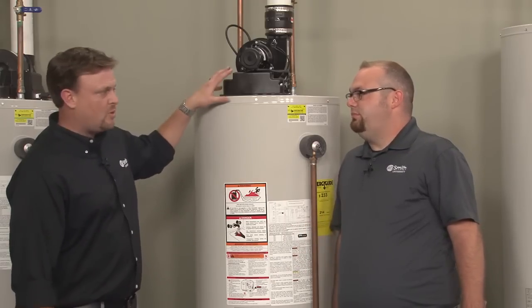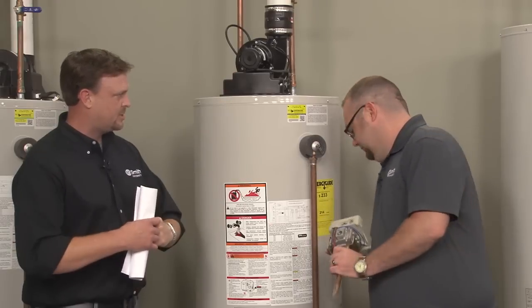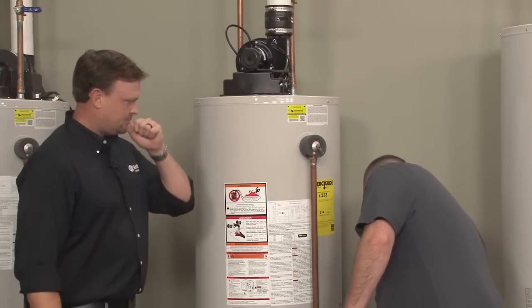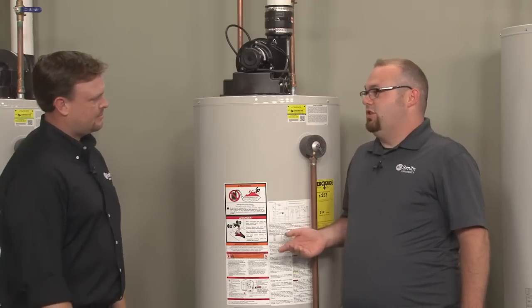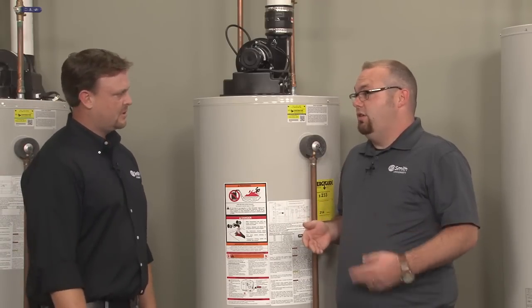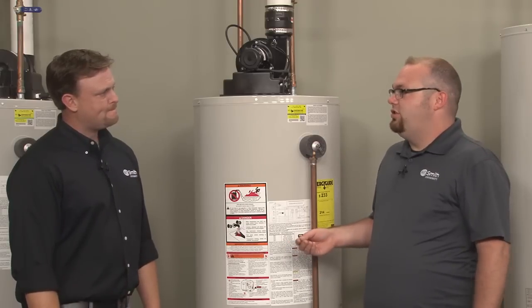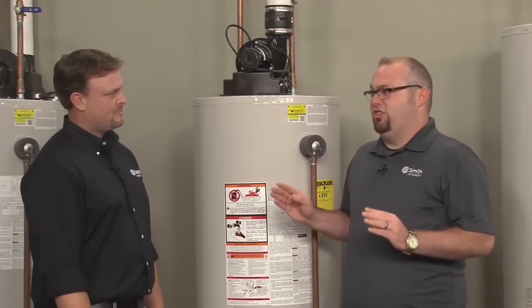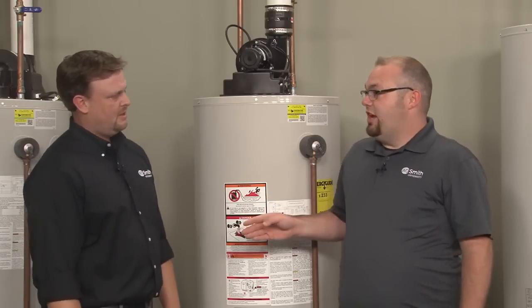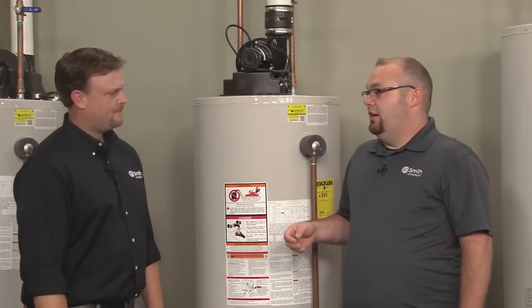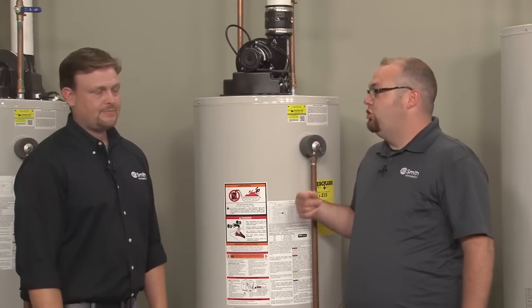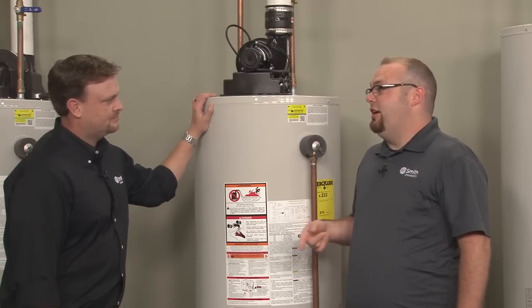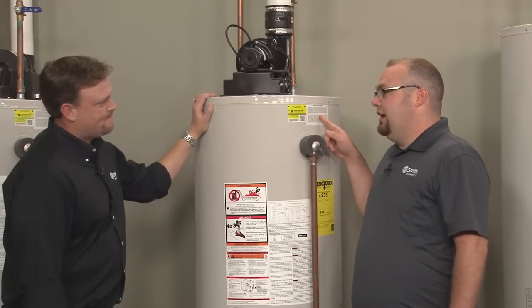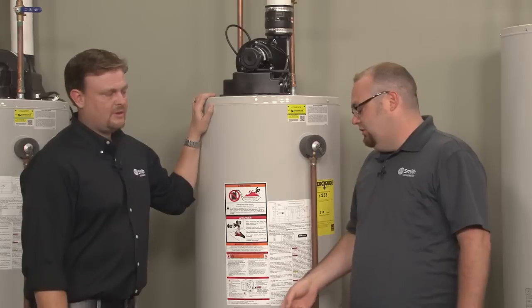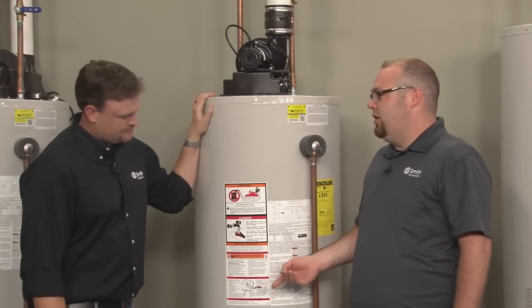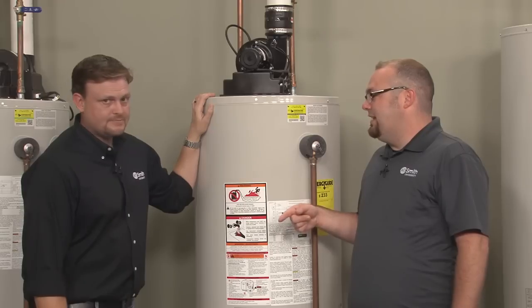So that means we're at the point when the blower is supposed to kick on and close the pressure switch. It never saw that. Correct. It never saw the pressure switch close, which it proved open. It just did not close. First thing I always check for, and this is where the heaters differ just slightly, is to see if the blower motor's running. On an IntelliVent, the older style valve, the blower should be running continuously. If it's not running, you have another problem. On this heater, the Honeywell, when it finally codes out on this code, it allows the blower to run for 30 seconds and then it kicks it off.